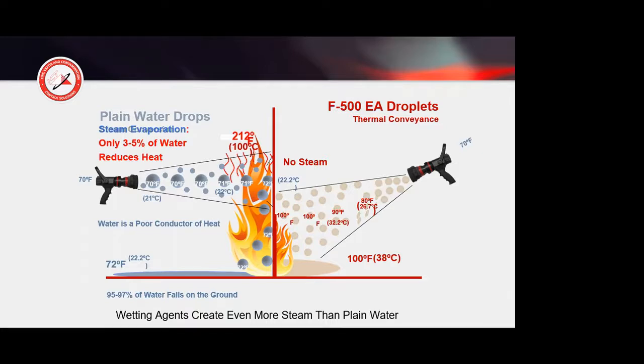So what we're doing is using the thermal conductivity properties of the F500, and we're pulling the temperature into the droplet. So here, if we come out at 70 degrees, the droplet becomes 80, 90, 100, because the temperature is going in the droplet and being transferred around the micelle and into the water molecules inside. So we get a rapid heat reduction, a very rapid knockdown of the fire, but one of the biggest benefits is the no steam creation.